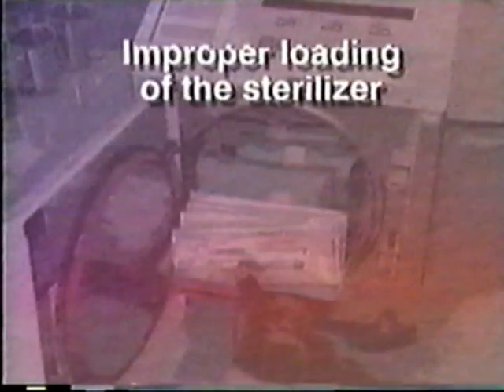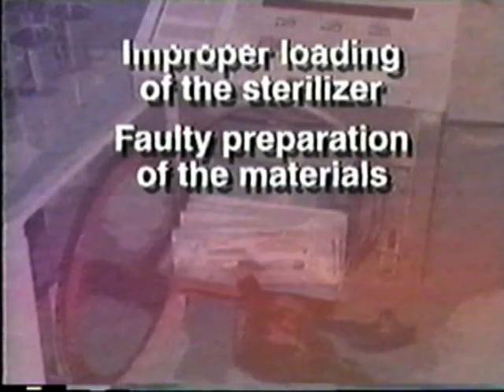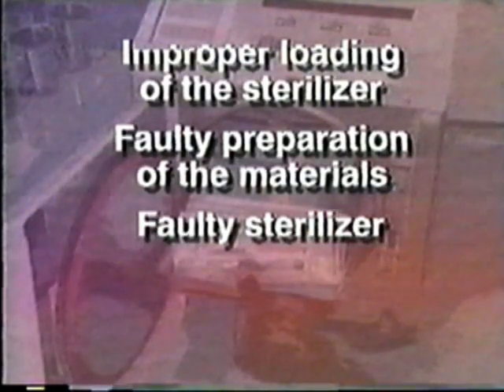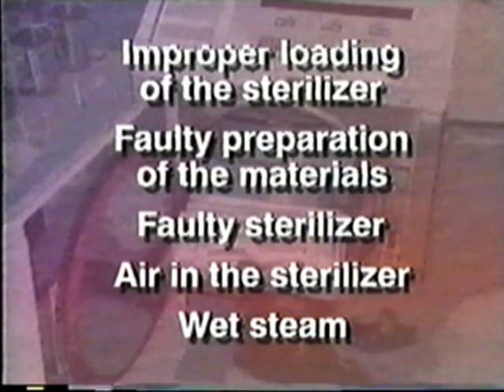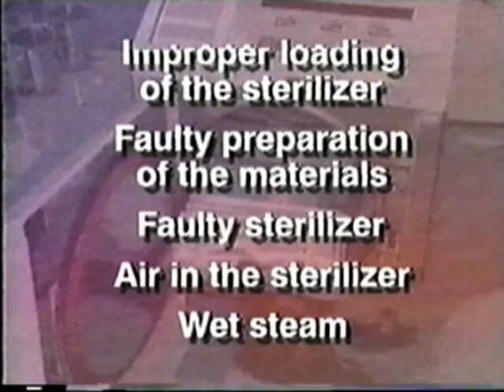This is a warning that there may be a sterilizer malfunction or an error in the sterilization technique. Never neglect this warning. Some of the most common problems are improper loading of the sterilizer, faulty preparation of the materials, a faulty sterilizer, air in the sterilizer, or wet steam caused by an excess of water in the boiler or pipes, which causes items in the sterilizer to become wet. Check for an error in your technique. If the indicators still do not change color, it may be necessary to have the equipment repaired.